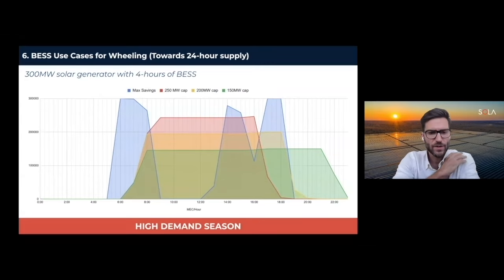So now that's a maximum savings type of profile, putting as much into peak. But what about when buyers want to start to match a flatter demand profile, if they want to have more coverage over the 24 hours, or if they want to have a higher renewable energy penetration? They want to save money, but that's not the only priority. They also want to have a more useful generation profile that covers more hours of the day. Well, this graph basically takes that same facility. We've increased the battery storage capacity from 2 hours to 4 hours.